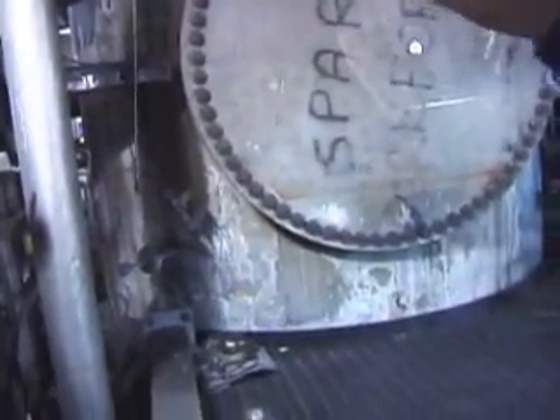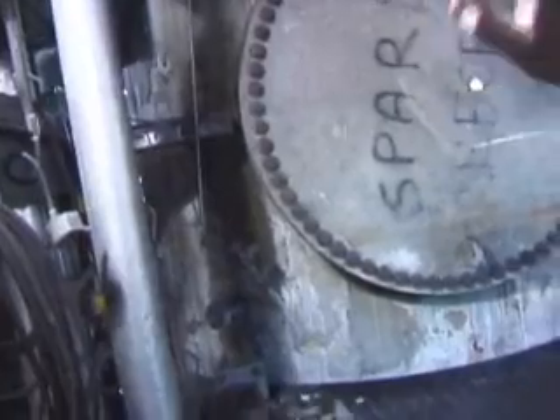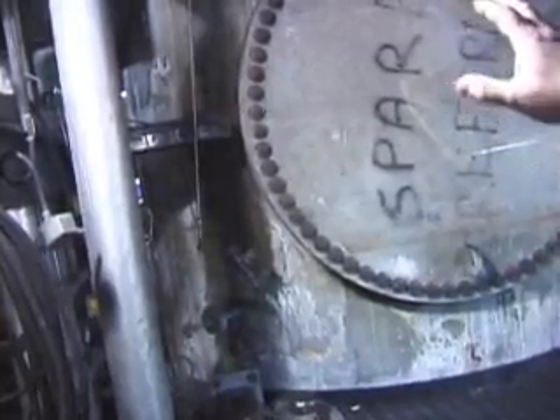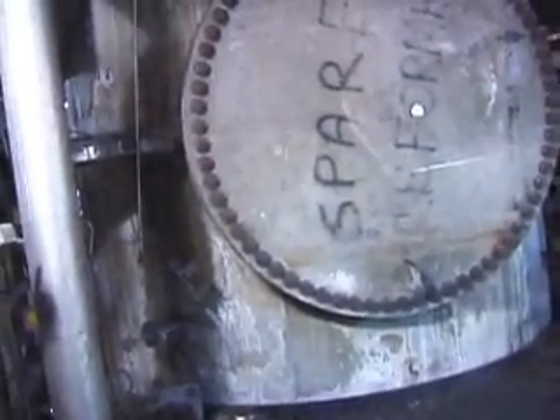This is the vessel here, and it's all full. The vessel weighs about 100 tons. There's about 60 tons of refractory, 30 tons of heaters, and there's about 100 tons of material in it. So it's about 300 tons sitting here. This is the heater that burned out.